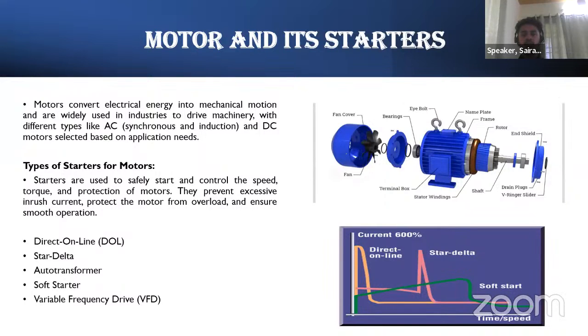Then coming to the motors and starters. Motors are devices that convert electrical energy into mechanical energy, which helps us in several ways in doing our work at the industries. Starters are used for initiating the operation of the motors. Starters are usually used to safely start the equipment until reaching the desired speed of the motors. Initially there will be a surge current, higher current consumption at the motors, so to prevent the problems of those starting conditions, these starters will be used.